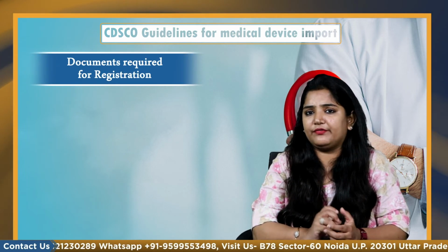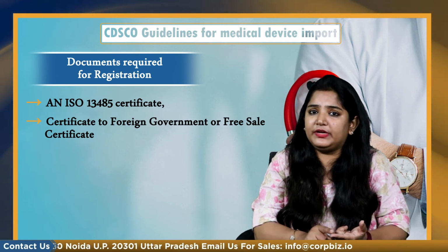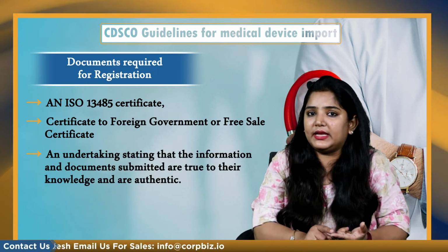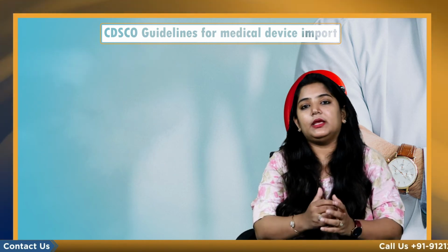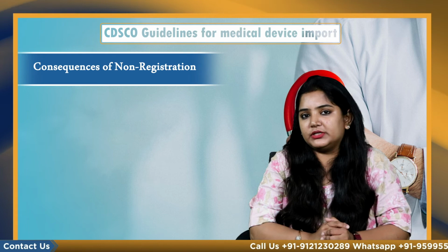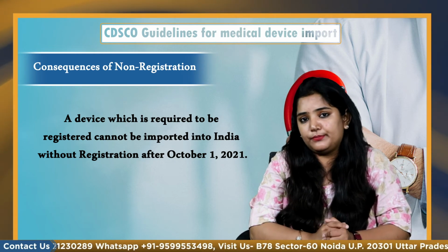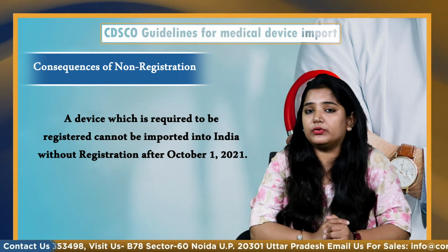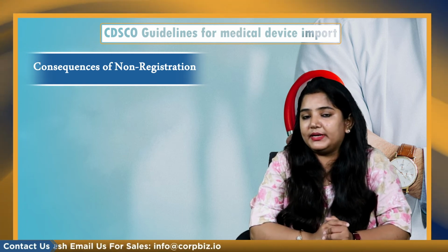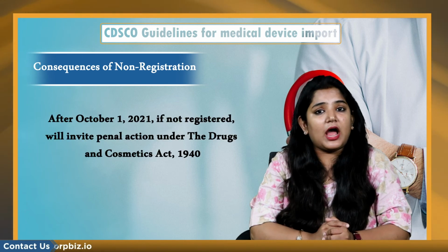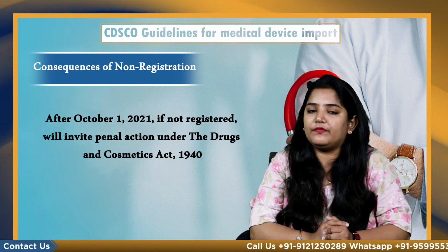The basic documents required for registration are an ISO 13485 certificate, a certificate of free sale from a foreign government, and an undertaking stating that the information and documents submitted are true to their knowledge and authentic. Let's see the consequences of non-registration as per CDSCO guidelines. A device which is required to be registered cannot be imported into India without registration after October 1, 2021. Importers need to get registration done before they import medical devices to India. Devices imported after October 2021, if not registered, will invite penal action under the Drugs and Cosmetics Act of 1940.